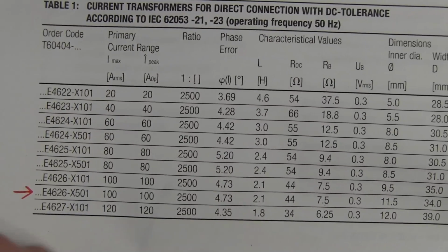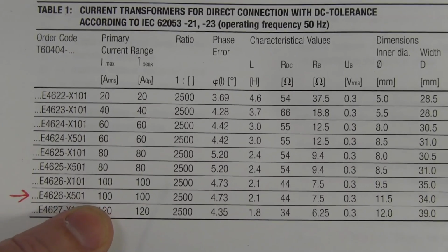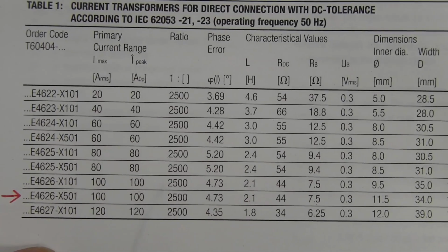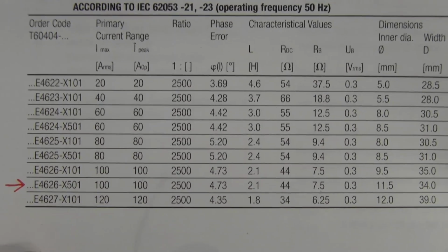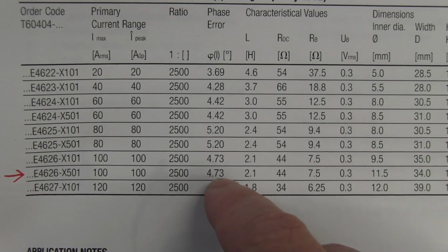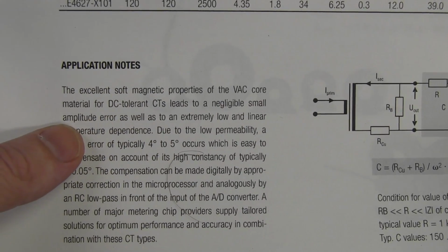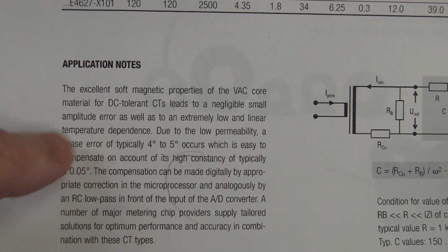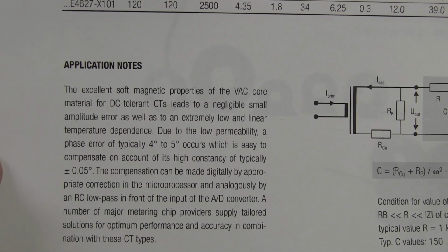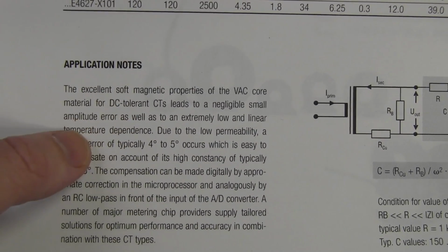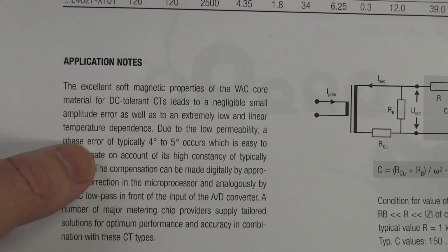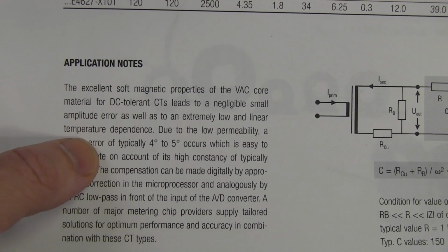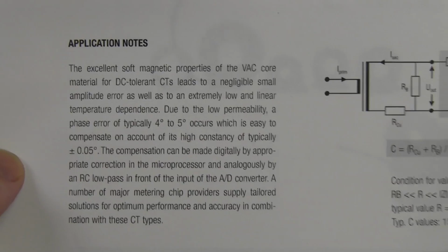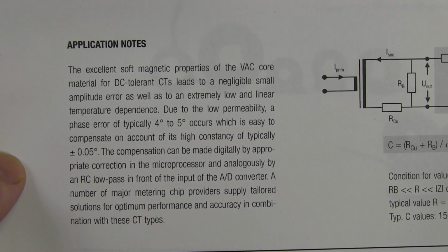So you divide the 100 amps by 2500, and we're going to get 40 milliamps maximum on the output. They have pretty much essentially a fixed phase error due to the excellent soft magnetic properties of the VAC core, as it tells you down here. These are DC tolerant current transformers, leading to a negligible small amplitude error, as well as an extremely low and linear temperature dependence. They've got all the curves in here for the temperature dependence and stuff like that.